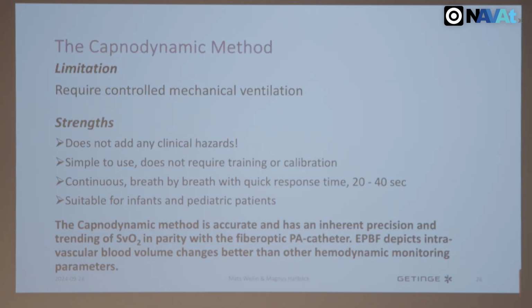So the capnodynamic method is promising, but has a limitation: it requires controlled mechanical ventilation. But it has strengths. It doesn't add any clinical hazards. It's simple to use, and does not require any training or calibration. It continuously gives you breath-by-breath new measures, and has a short response time.